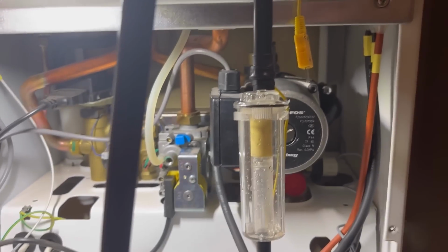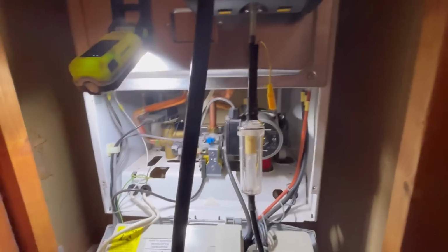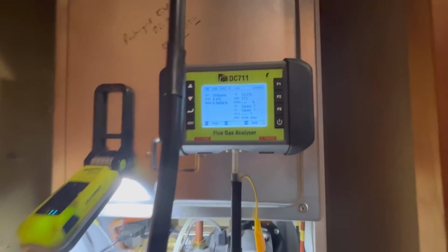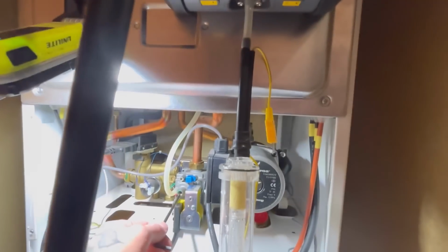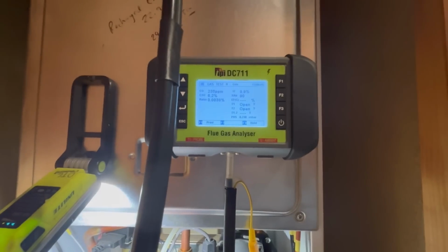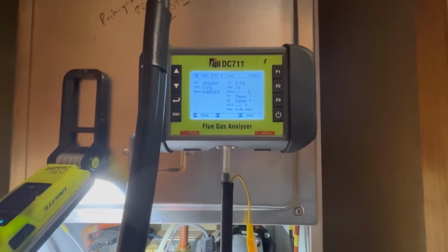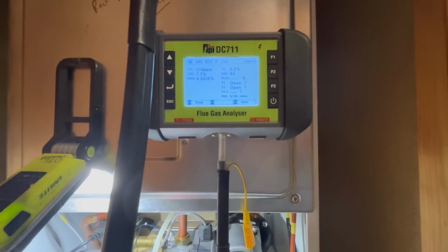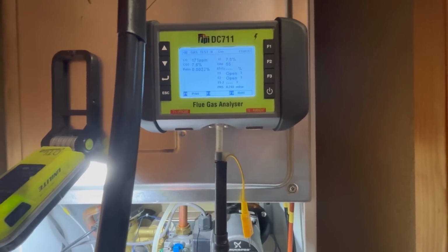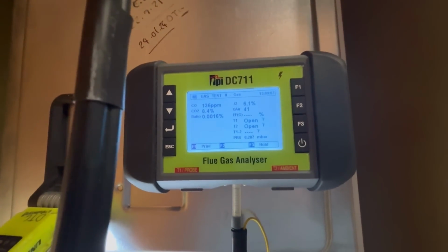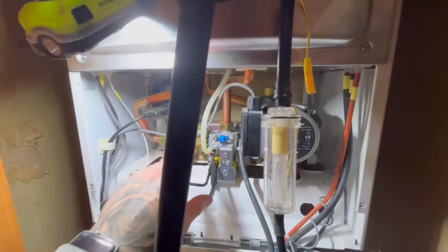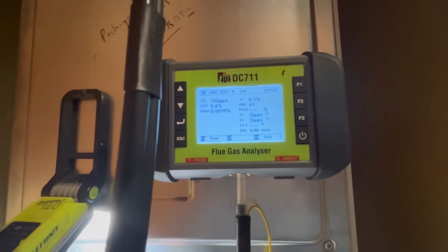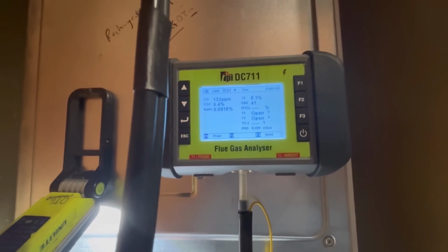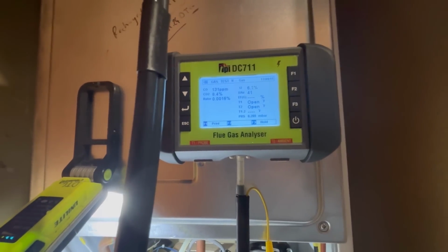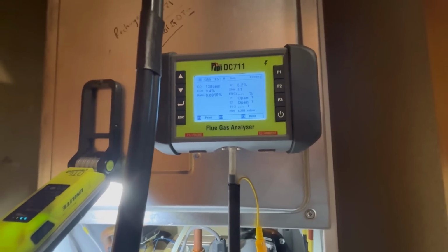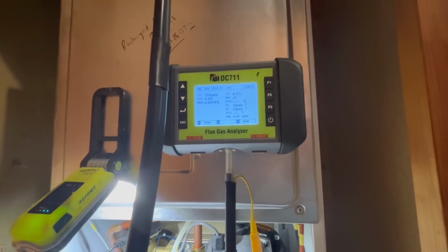Not done anything yet, but put it back into minimum mode. We'll look at the state of them readings. It's coming back down now, thank God. I'm going to try and throttle it down to like 8.3, 8.2. They're still quite high then for a minimum. 130 parts per million is very high.